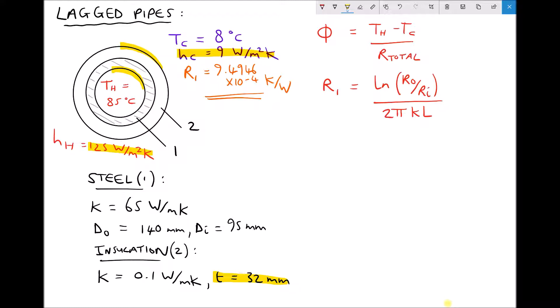As the data for the steel pipe is unchanged, our thermal resistance for that layer remains unchanged, so it remains as 9.4946 times 10 to the minus 4 Kelvin per watt.